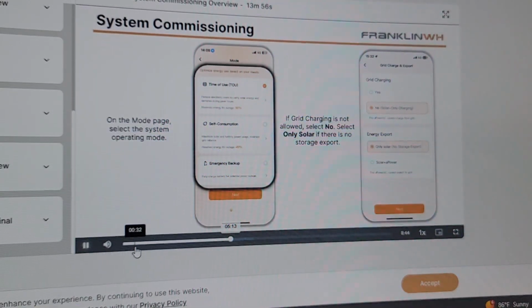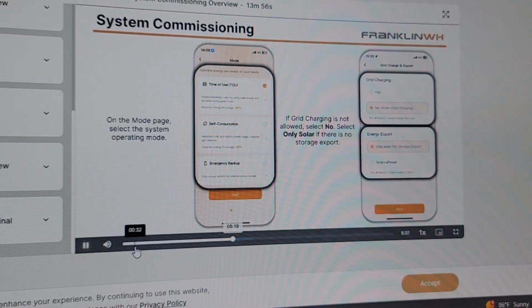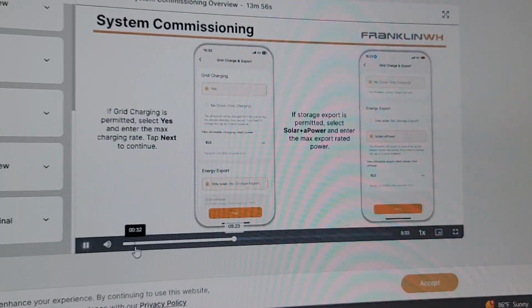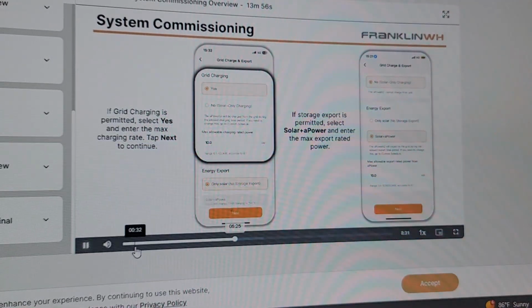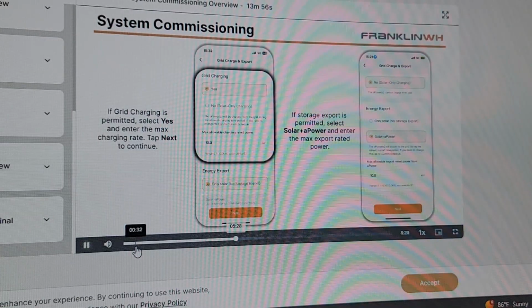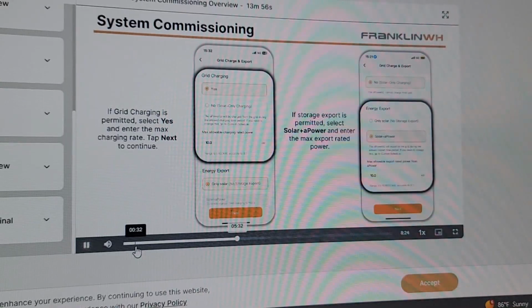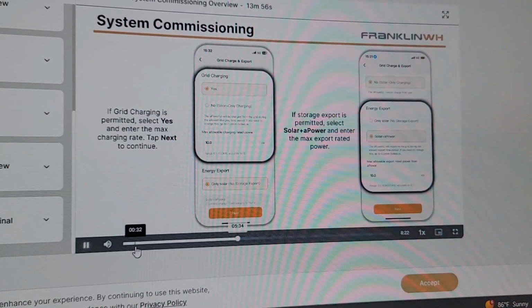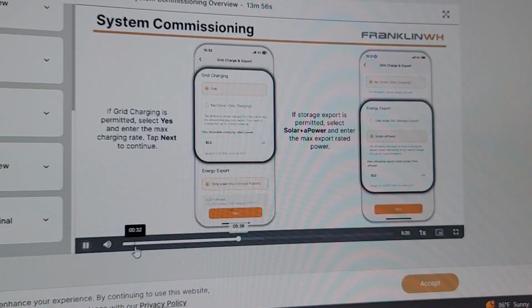On the Mode page, select the system operating mode. If grid charging is not allowed, select No. Select only solar if there is no storage export. If grid charging is permitted, select Yes and enter the max charging rate. Tap Next to continue. If storage export is permitted, select Solar plus aPower and enter the max export rated power.